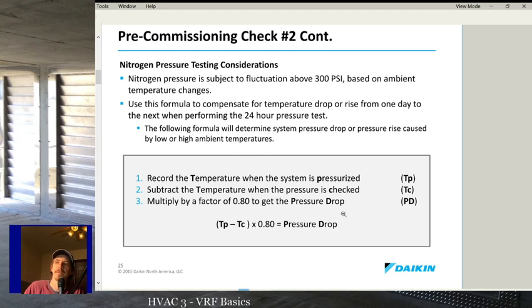Alright, so it's not much, but it's something. And if you're talking a 20, 30, 40 degree temperature difference, then that is a 15, 20, 30 PSI pressure difference. So that's a good way to shortcut instead of doing the whole gas law equation. It can still be done if you know the gas law. It's not that difficult, but this is still way simpler.